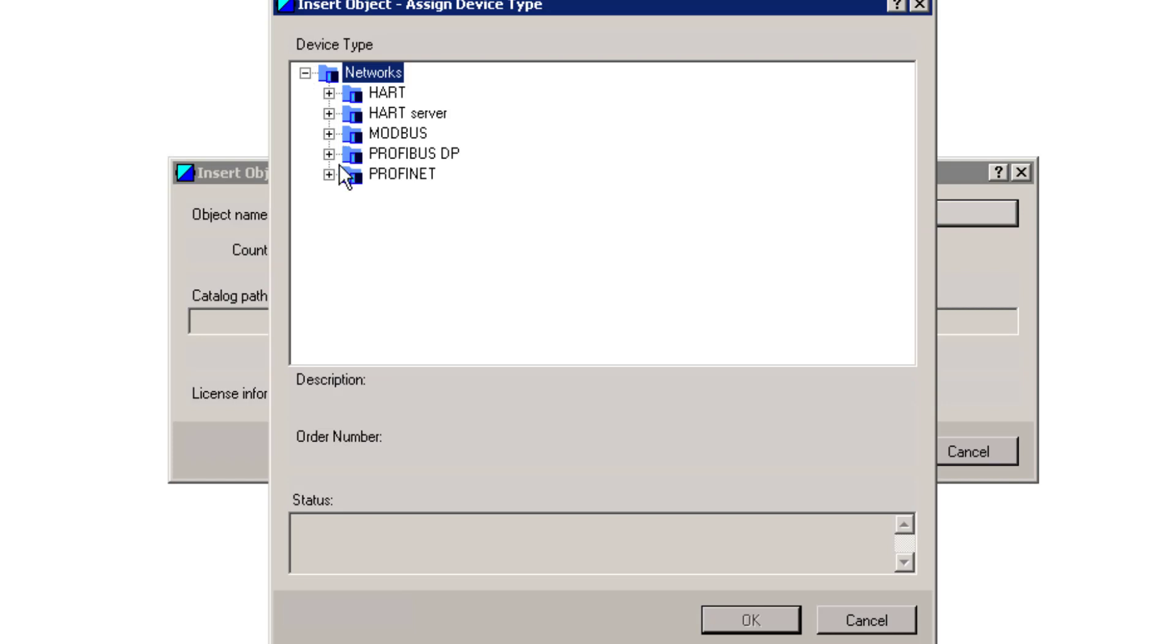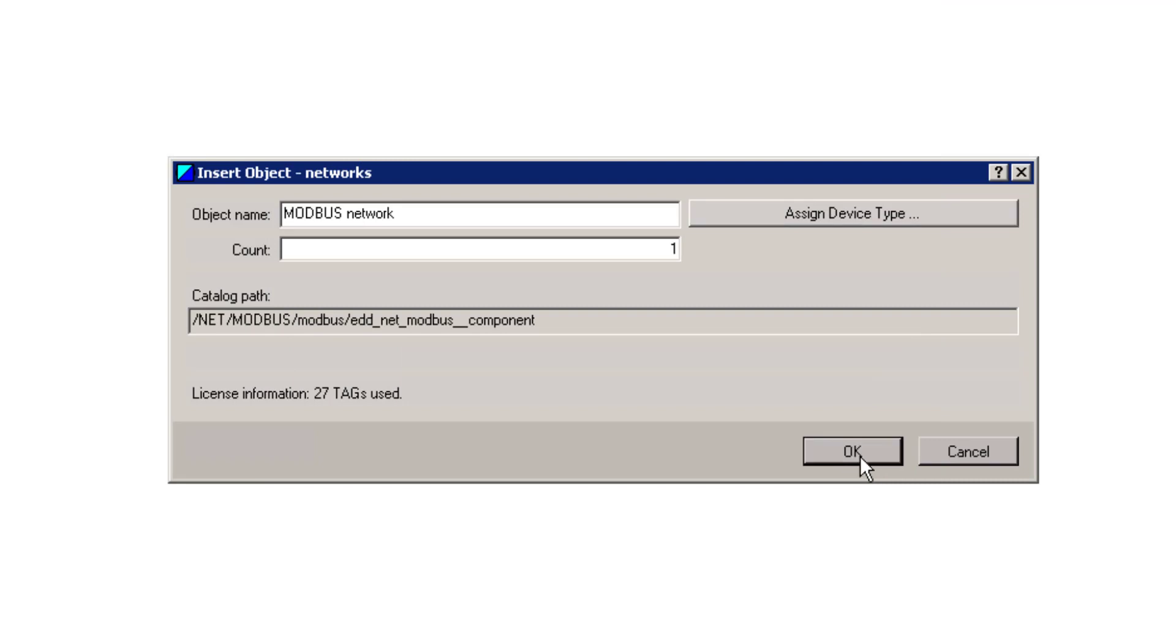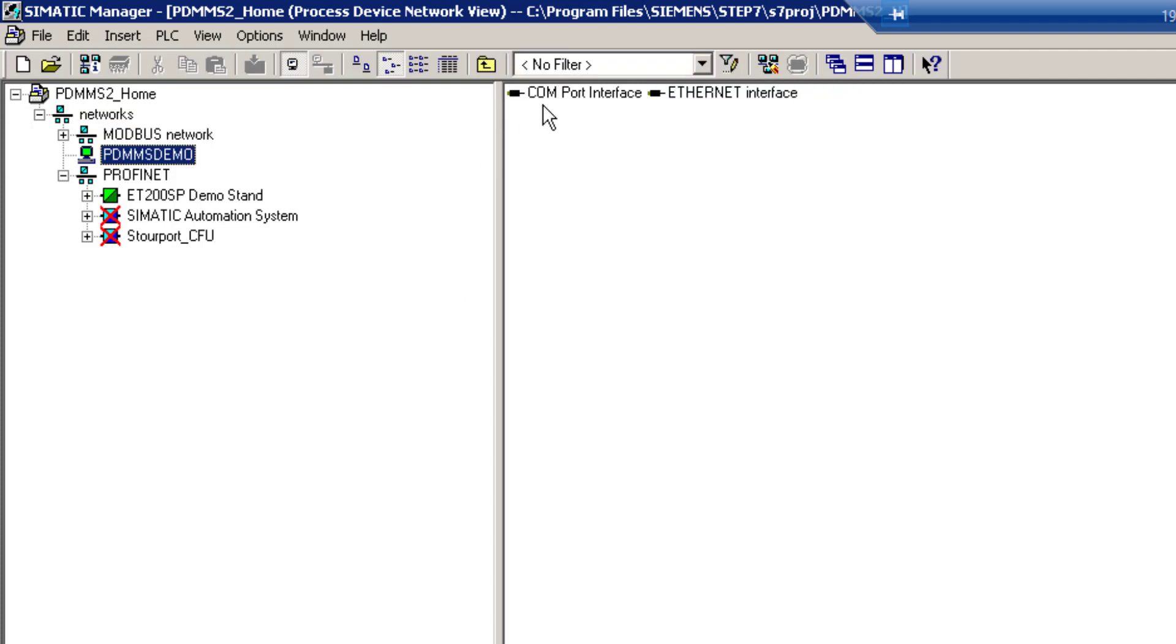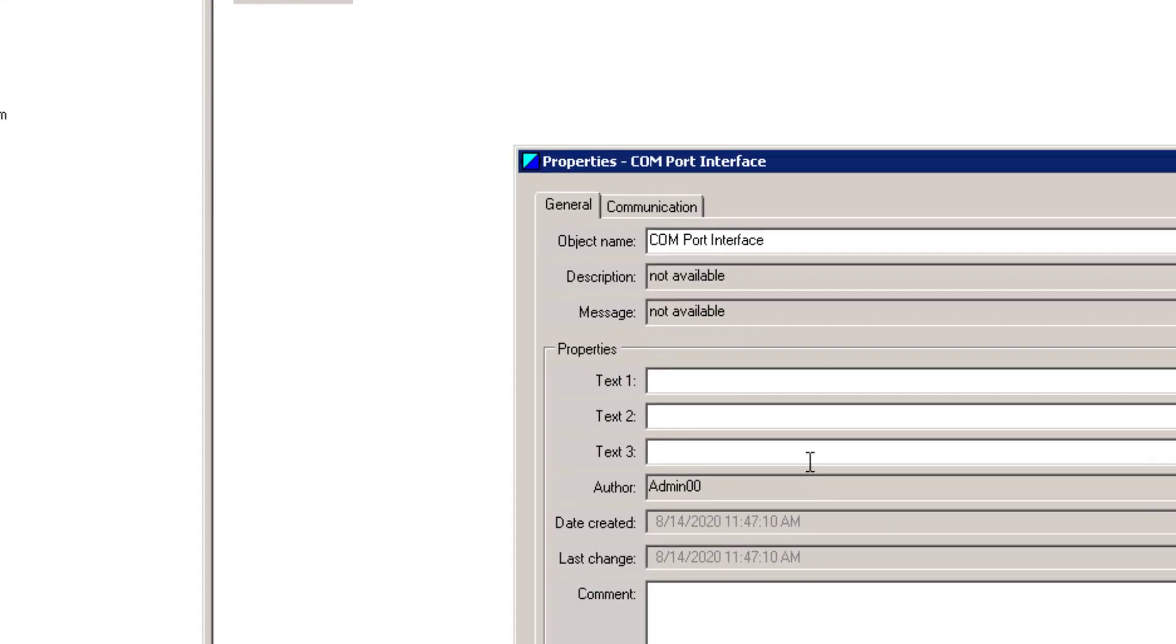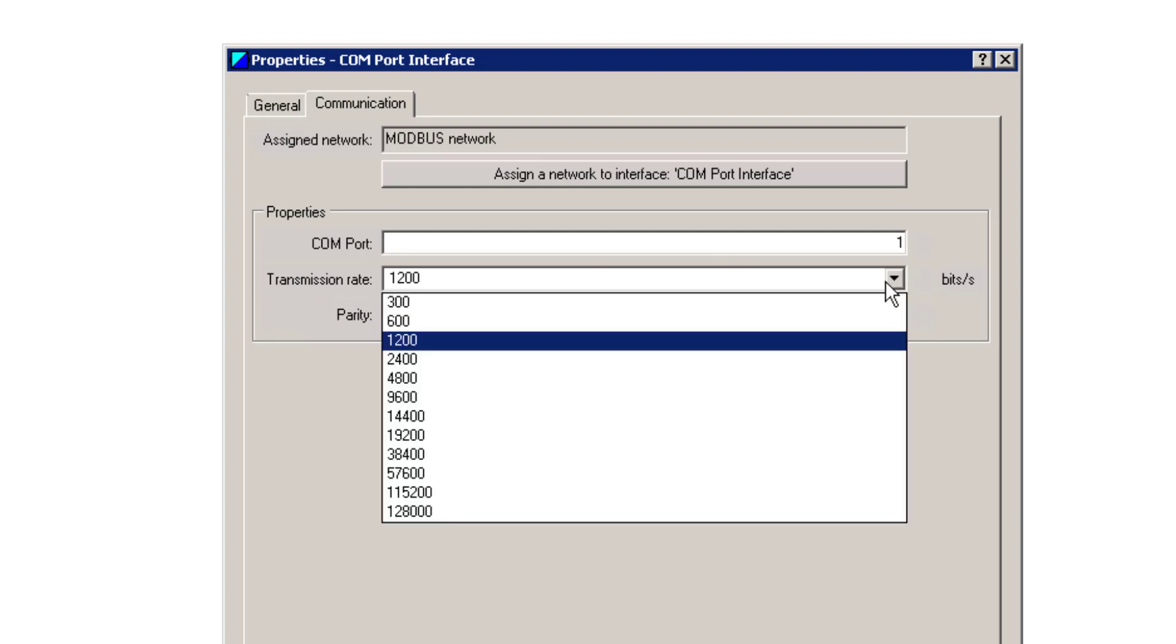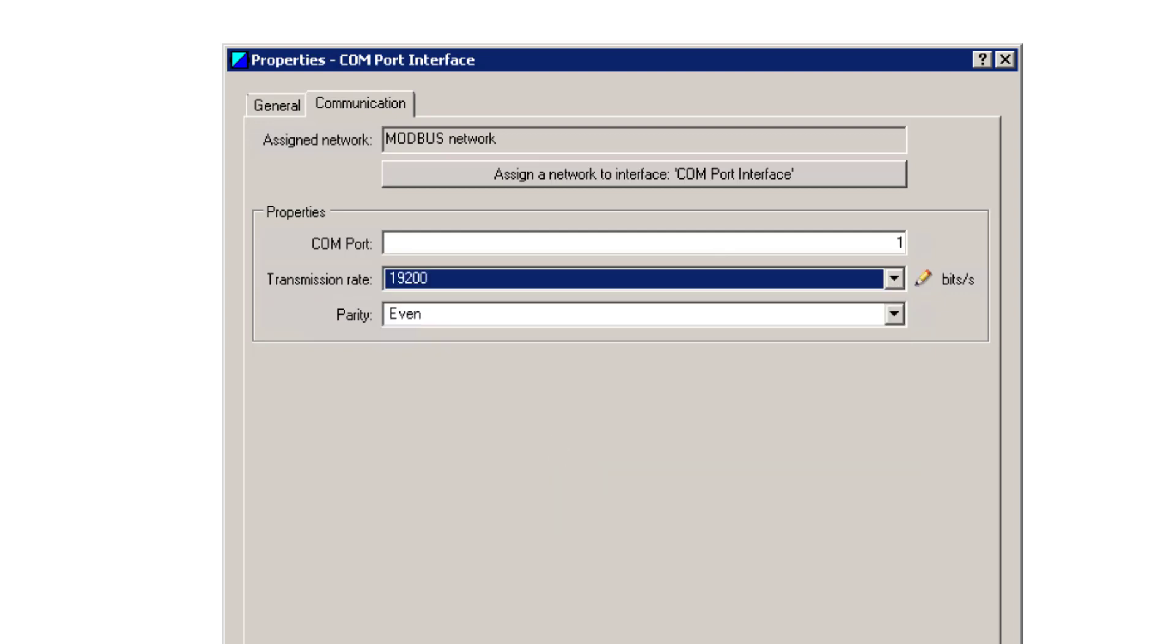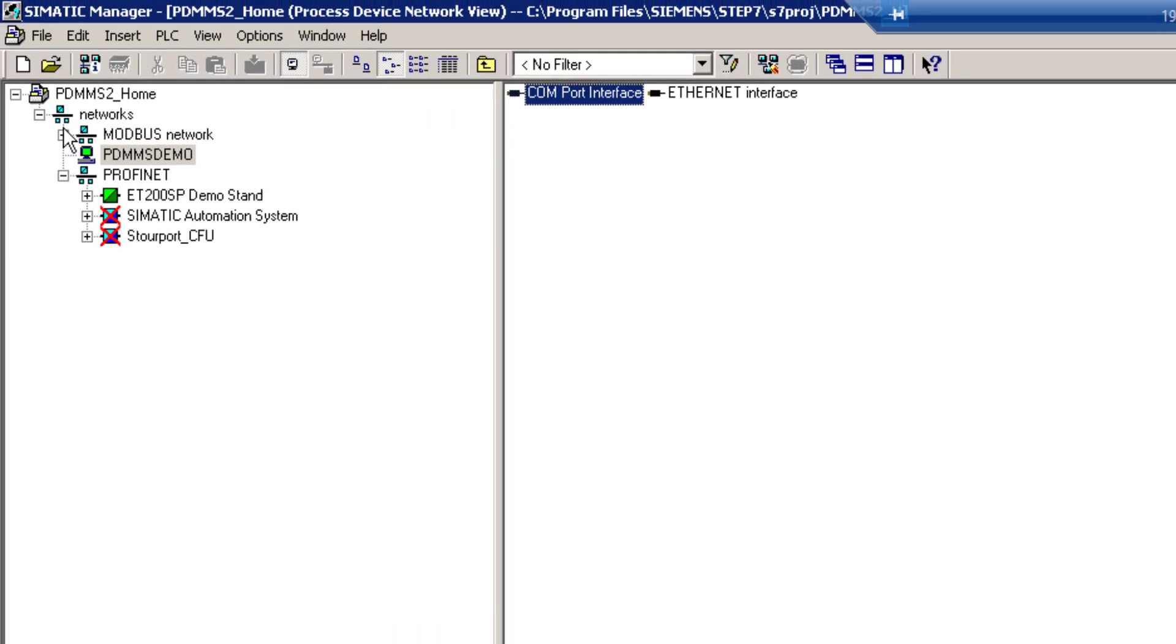That is going to be MODBUS. You can see here I have no selection for MODBUS TCP. That's the beauty of the virtual serial port. So we'll add that. Then we've got to make some changes. This is the one thing that we normally struggle with over tech support. If you click on the PC, you'll see under there COM port interface. Right click, go to object properties. Here under communication COM port 1. So this has got to match what you've got on your virtual COM port. Then you've got your transmission rate is 19200. And there you can see my MODBUS network.